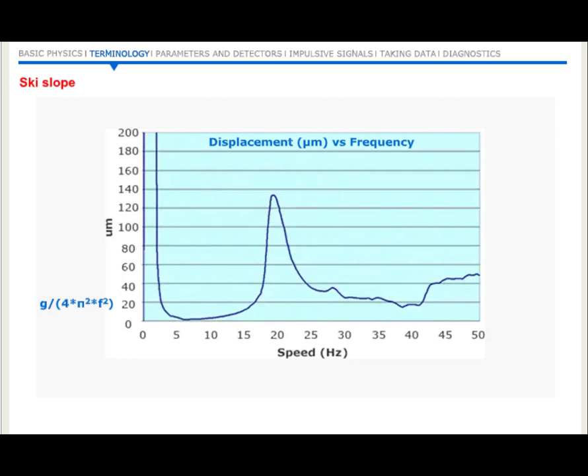Some accelerometers will emit a signal at 1 Hz or below, which is due to the ICP circuitry. When converting from acceleration to velocity, this signal gets amplified and values of 360 mm per second or even higher may be observed on the y-axis. To combat this, you can install a low-frequency filter.